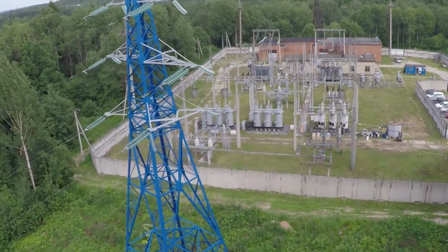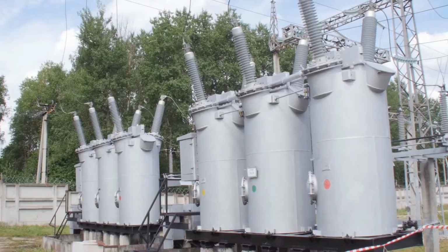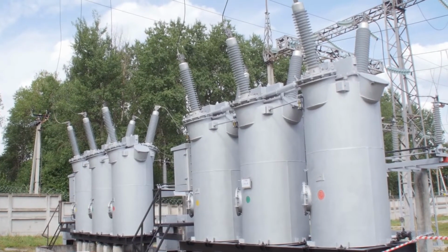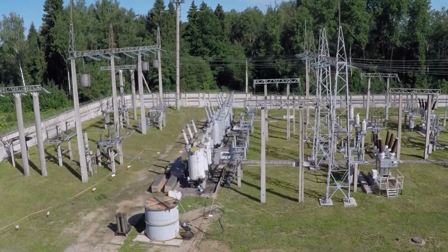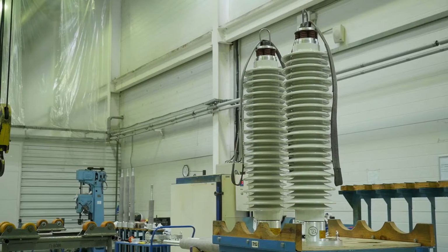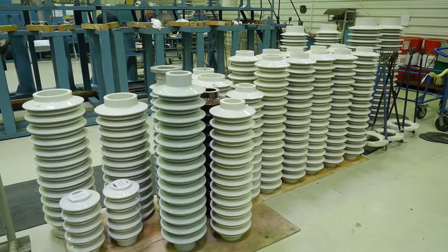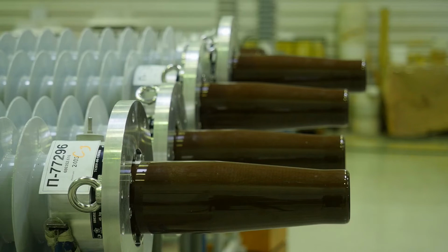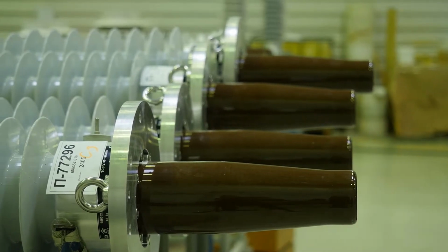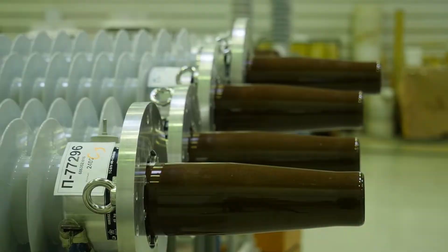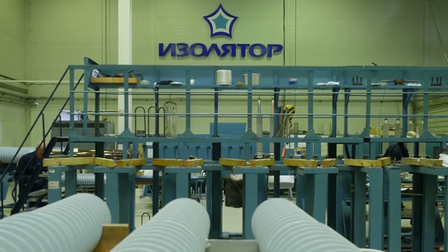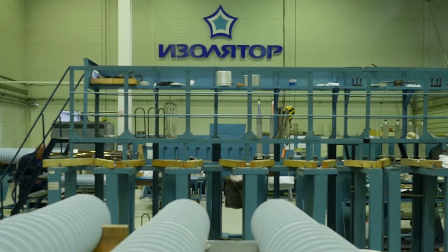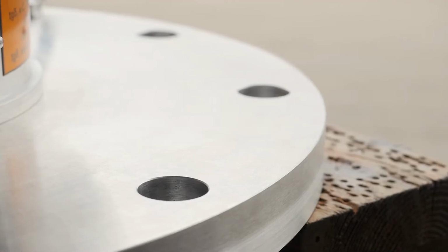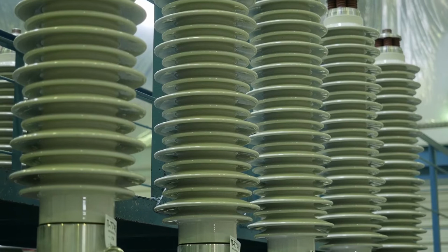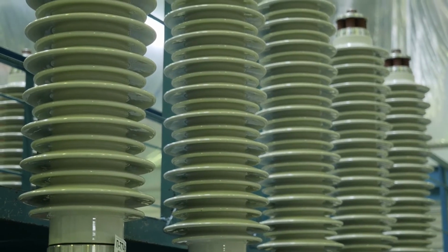The high-voltage bushing is one of the most critical structural components of the transformer, reactor, or oil circuit breaker, ensuring their reliable, failure-free, and long-life operation. Internal insulation is the main structural part of the high-voltage bushing, defining its technical properties and performance. Nowadays, a solid RIP insulation is its most advanced version. Compared to others, bushings with this insulation are highly reliable and durable due to low dielectric losses and partial discharge factor, as well as to its thermal resistance.